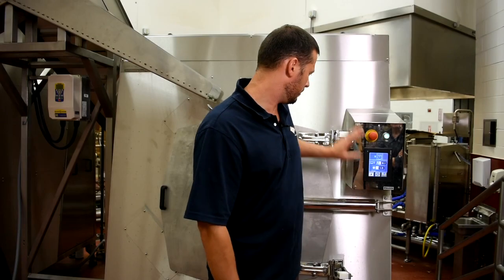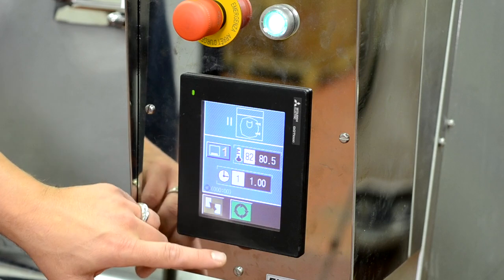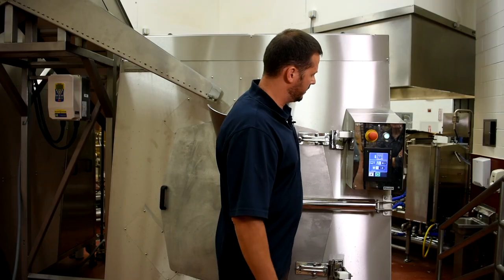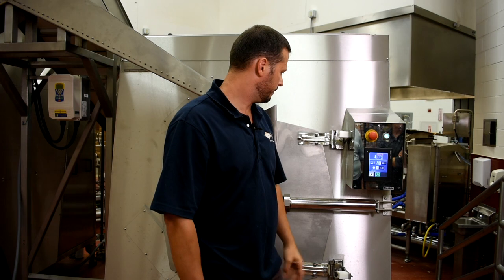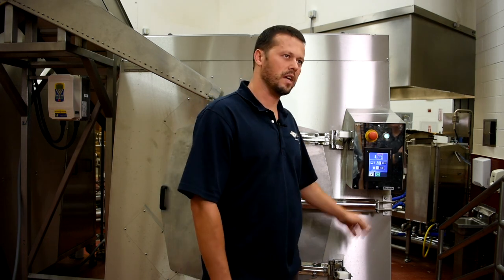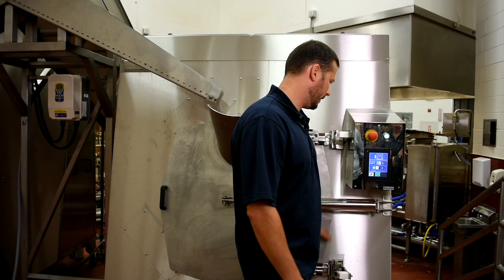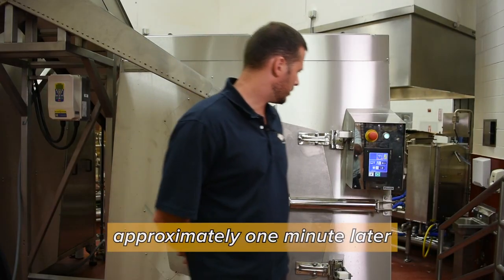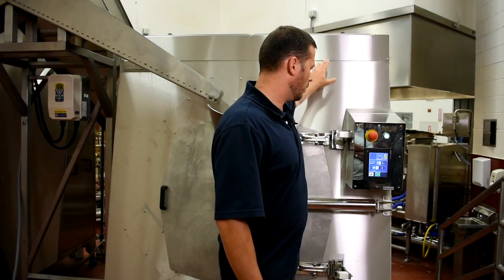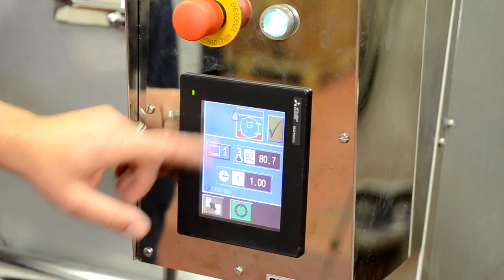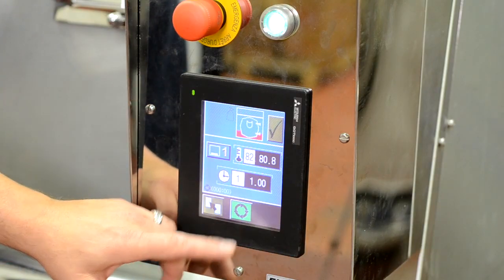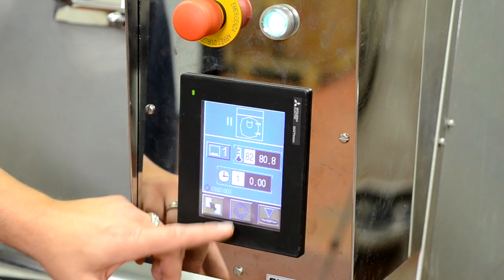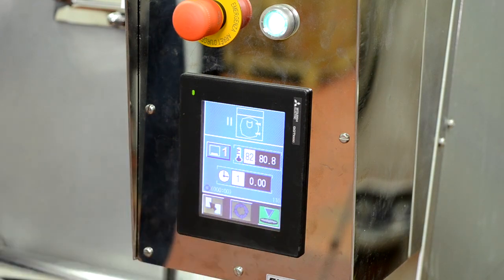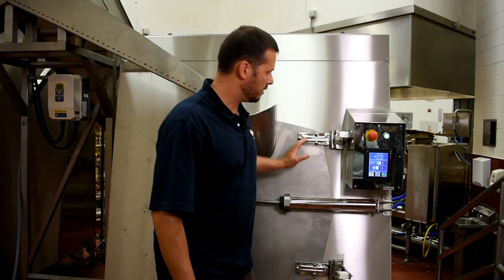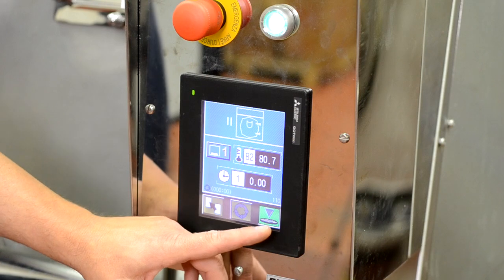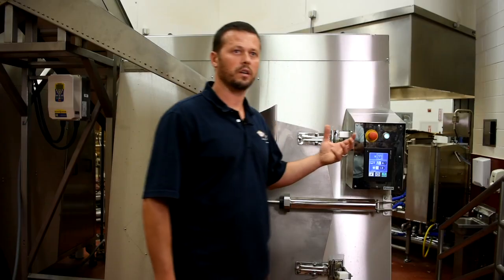Okay, so we just paused the process, and we'll restart again. Now it's taking all the water from the upper tanks and putting it in the lower tank. And once this is done, we'll show how to drain the water from the lower tank. Okay, so right now the machine brought the full water back down to the lower tank, and now it's asking if we want to add the bags in here. Well, what I can do is stop the cycle at any time. I can stop the cycle, and there's a drain button, and we drain. And as soon as the water is completely out of the tank, this button will disappear and the door button will appear, and then we can open the door.